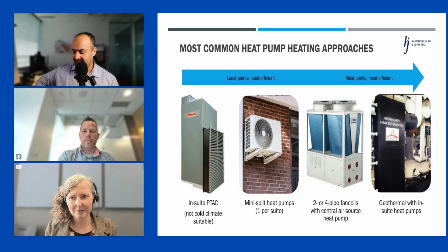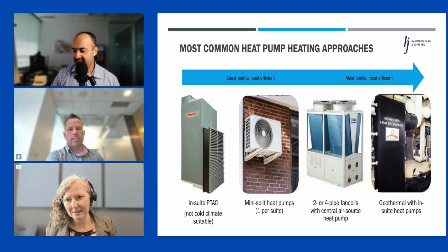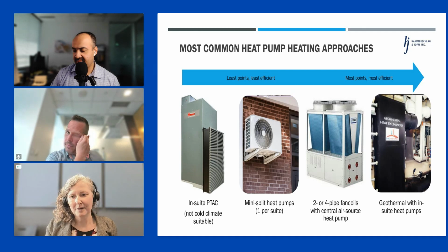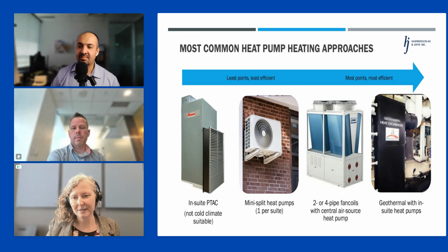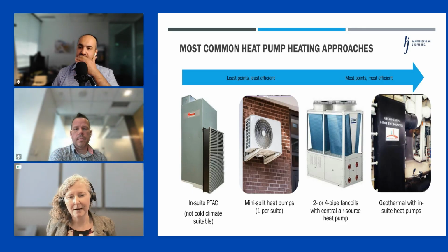So we phased out a number of refrigerants on Jan 1, 2025. It is only 10 months later. The offerings out there are widely varying. There are some countries that have banned some of the most popular transition refrigerants because they create what some people are calling forever chemicals that we see building up in waterways. So it may be that you'll jump to a piece of machinery that's using a refrigerant that then rephases out sooner than we expect. So these are a solution that gives you really good energy performance.